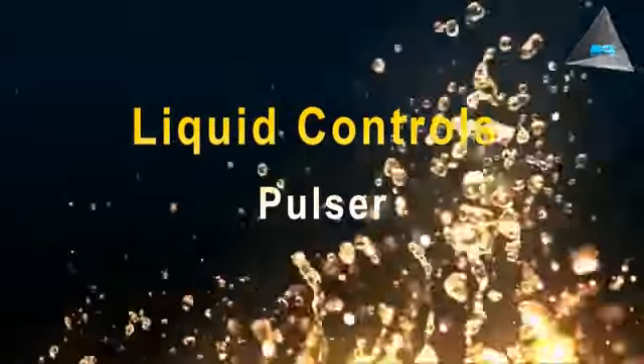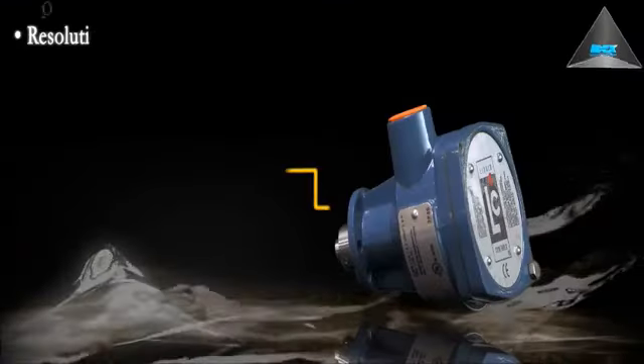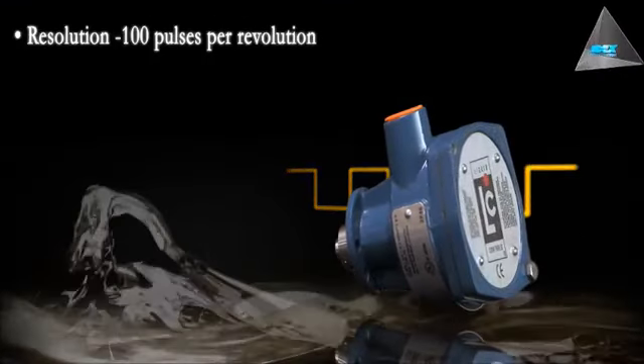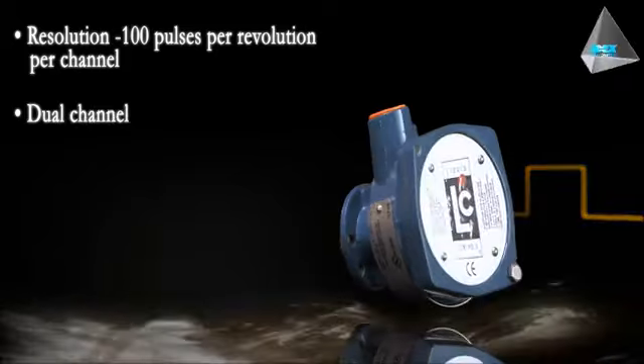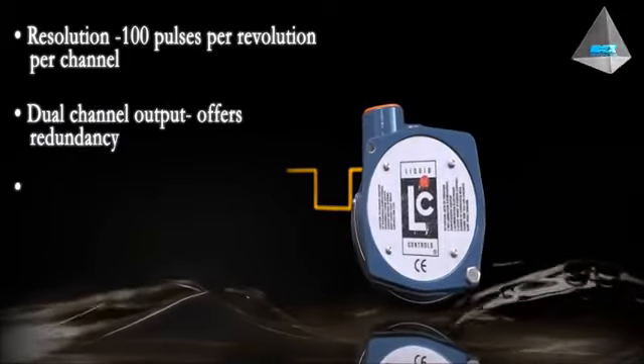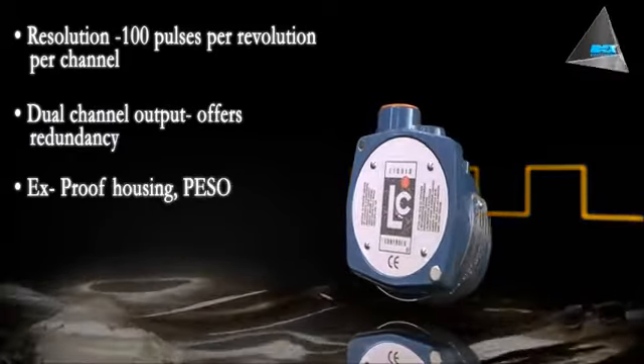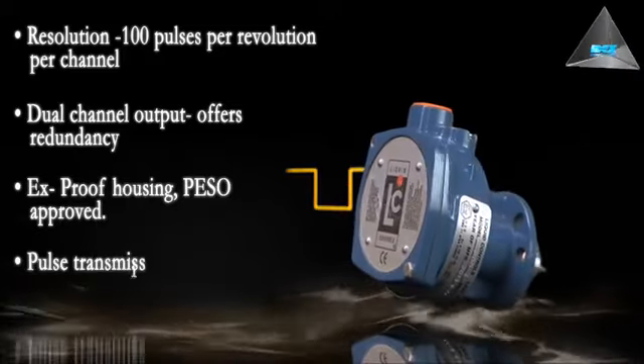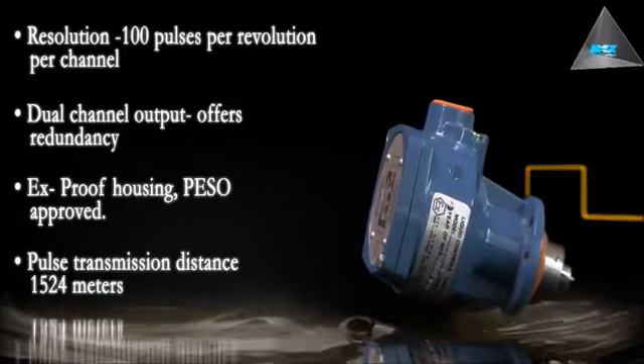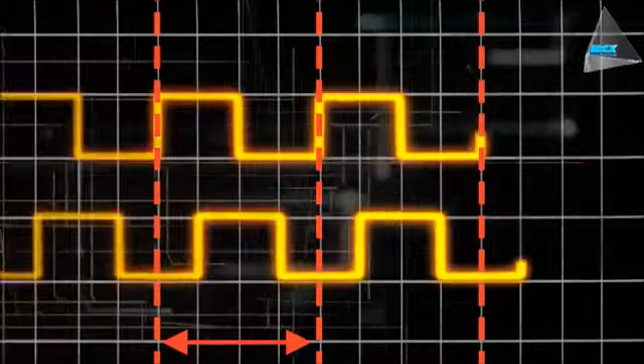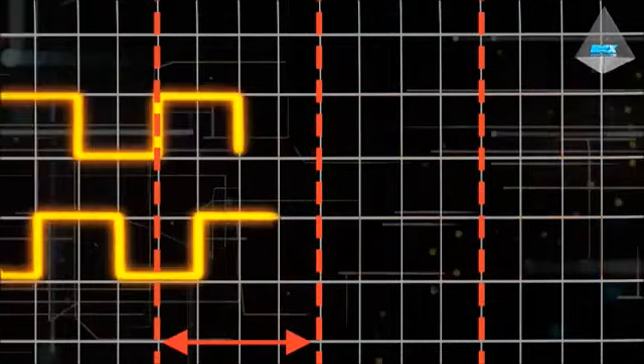Liquid Controls Pulser. Resolution 100 pulses per revolution per channel. Dual channel output offers redundancy. Explosion-proof housing, PESO approved. Pulse transmission distance 1524 meters. 90-degree phase shift between each channel. Pulse security feature for custody transfer.